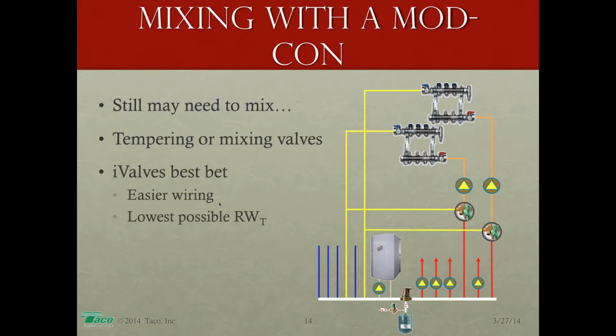So not only do we have boiler reset for the high temperature stuff, we also have system delivery reset, outdoor reset for the high temperature radiant, so it'll be 135 on the coldest day of the year. But as it gets warmer out, that temperature will drop, based on outdoor reset, and we'll have 110 on the coldest day of the year for the radiant slab. But as it gets warmer out, that temperature will drop as well through the control on each head. So I'd have outdoor reset for the boiler, outdoor reset for each of my radiant delivery packages.